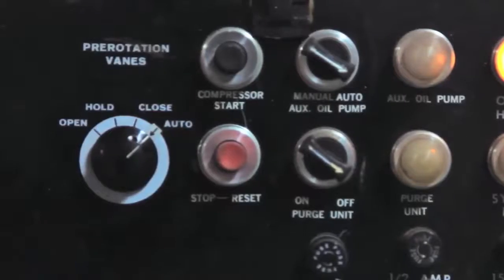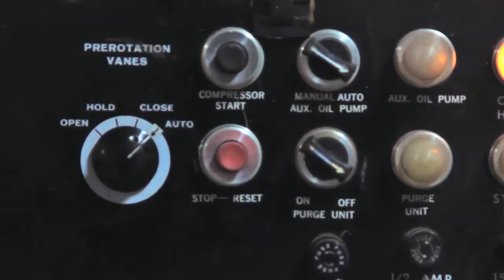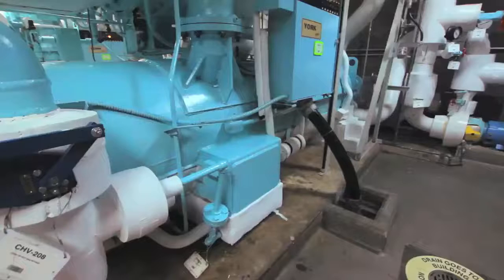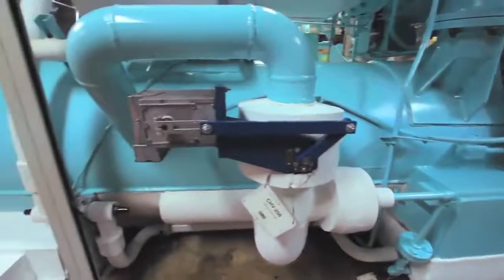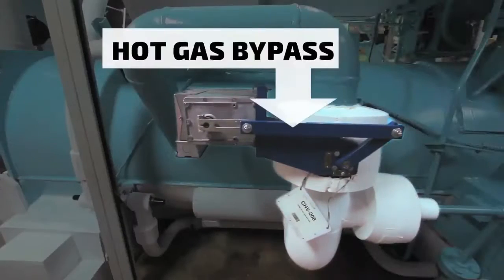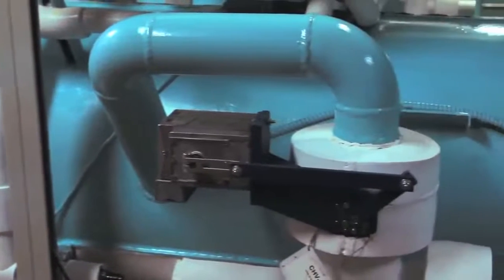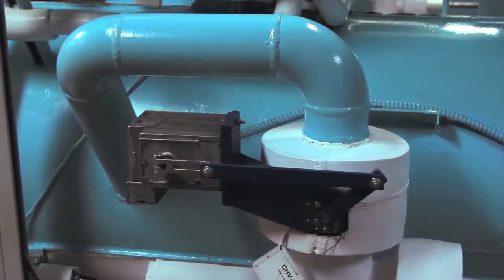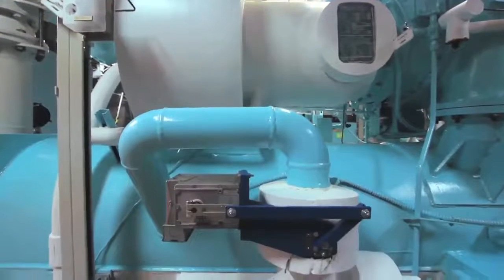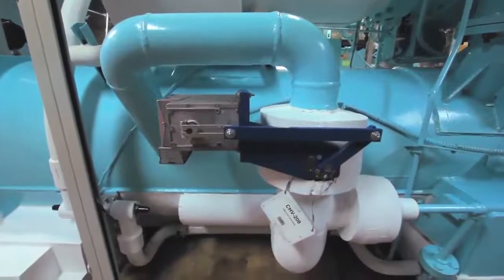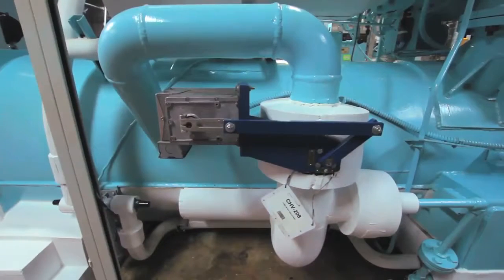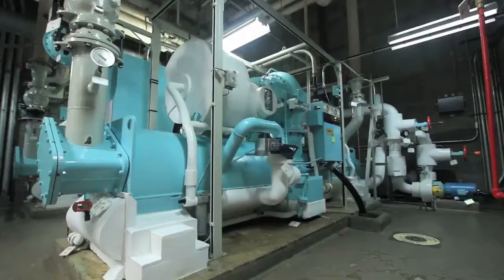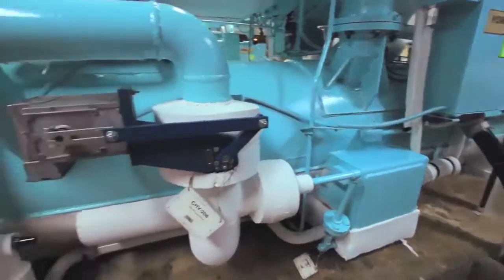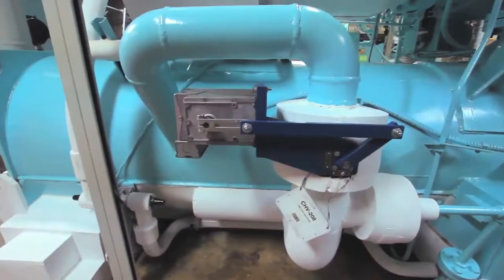Two of the operations we control are the iris, that's the compressor inlet vanes I talked about earlier, and the hot gas bypass. The hot gas bypass is a unique function. Because of the design basis requirements, the chiller must operate over a wide range. If you have no load on the machine, the cooler pressure will drop to a point where the machine can't function. Operating under very low load may cause the chiller to trip. These machines are not good at starting and stopping, so you want to keep it running. In order to keep it running, we use the hot gas bypass device.